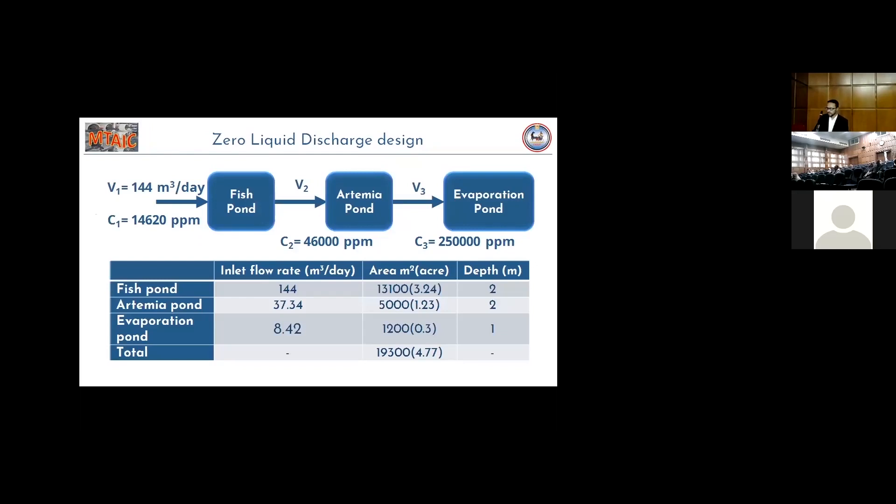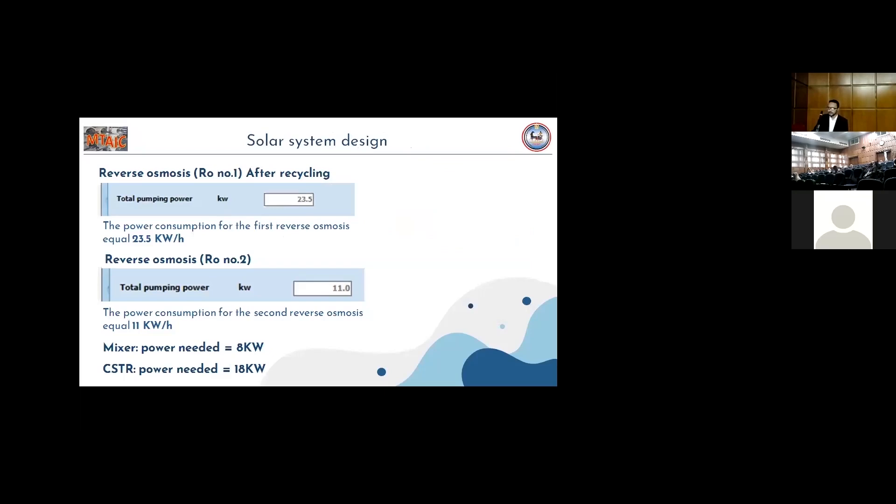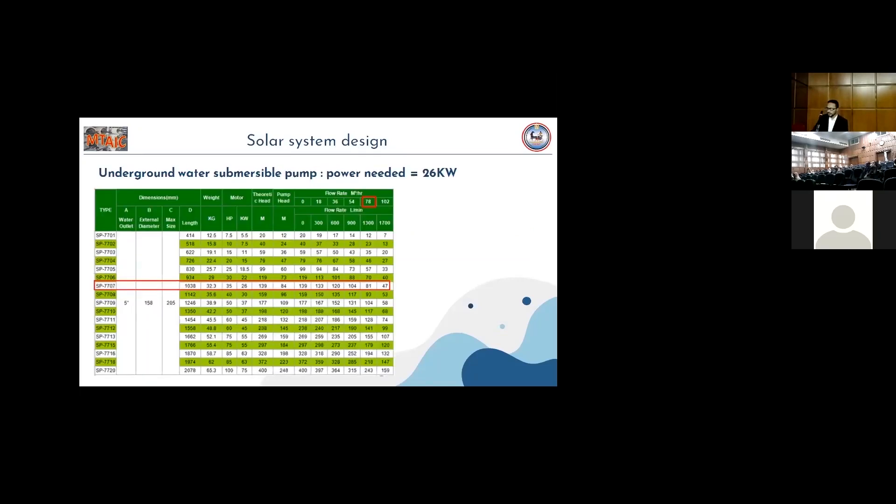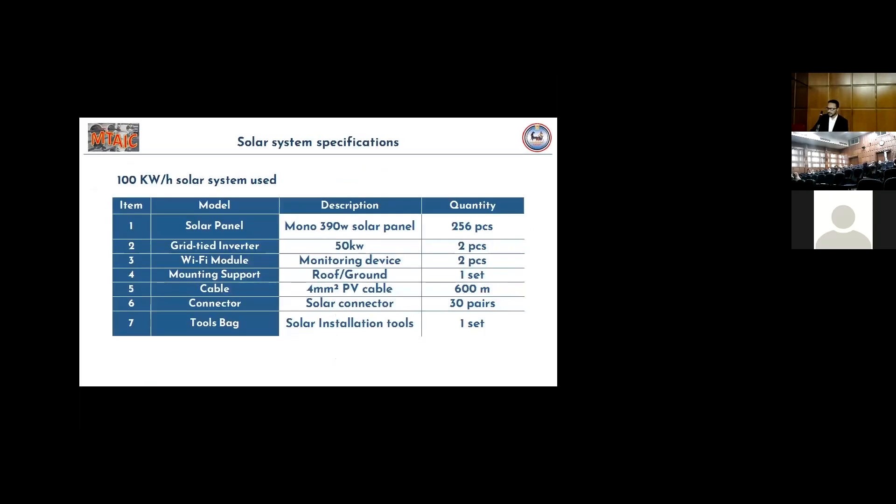The zero liquid discharge design includes three parts. First, the fish pond that can handle up to 46,000 ppm. And then, Artemia pond that can handle higher TDS range and evaporation pond. As the design is based on the evaporation rate in Egypt, the area needed for the whole system is 4.77 acres. The solar system is designed to provide the power required in RO pump and in the stirring part in the mixer and the stirring tank and the underground pump and backwash pumps. A 100 kW solar system is designed with its specifications.